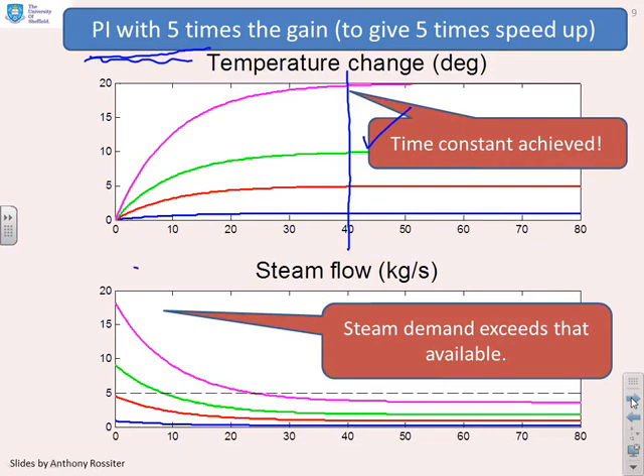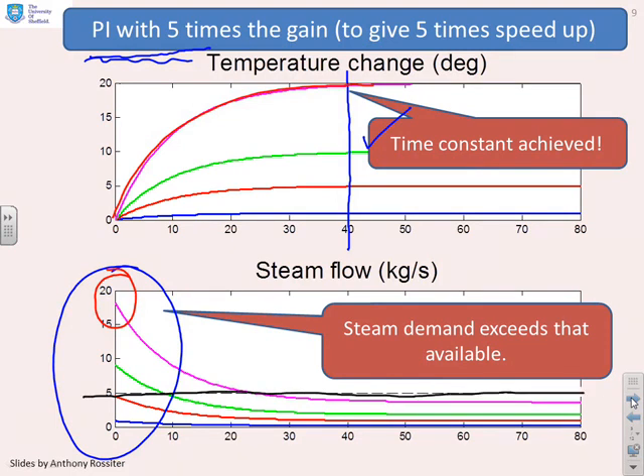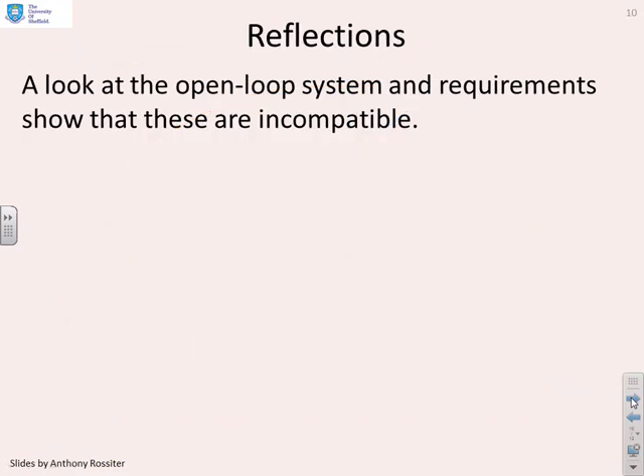However, where's the downside? If you look at the steam flows which the PI is requiring, you'll notice that in order to get a 20 degree uplift in temperature, the initial steam flow is getting pretty close to 20 kilograms per second. However, we were told you can't have more than five kilograms per second. In other words, the PI compensator is demanding much more steam than you can actually deliver.